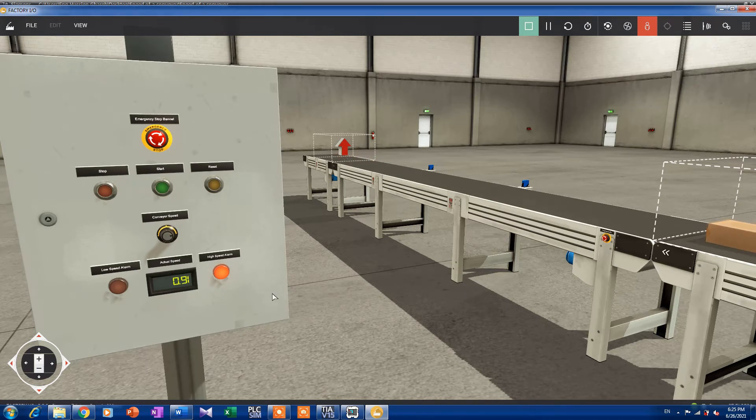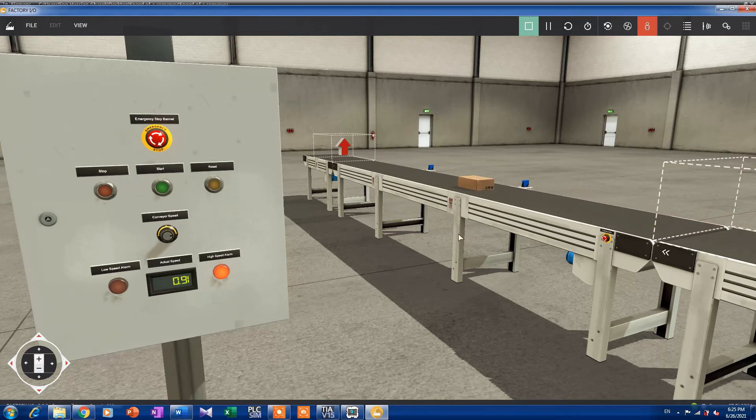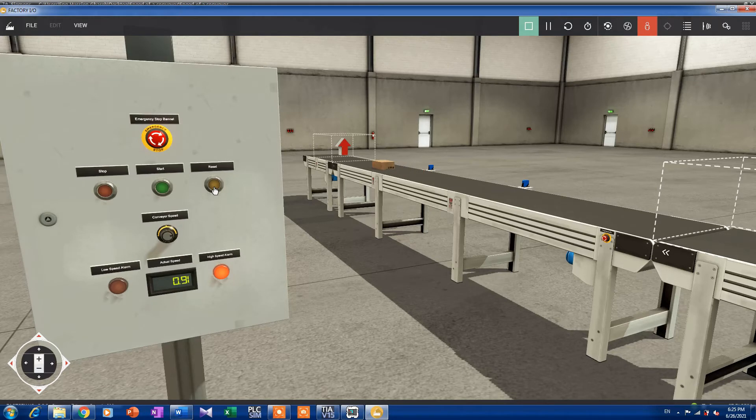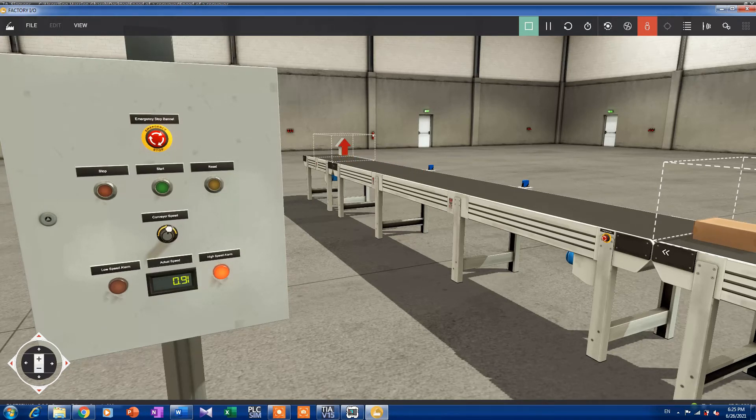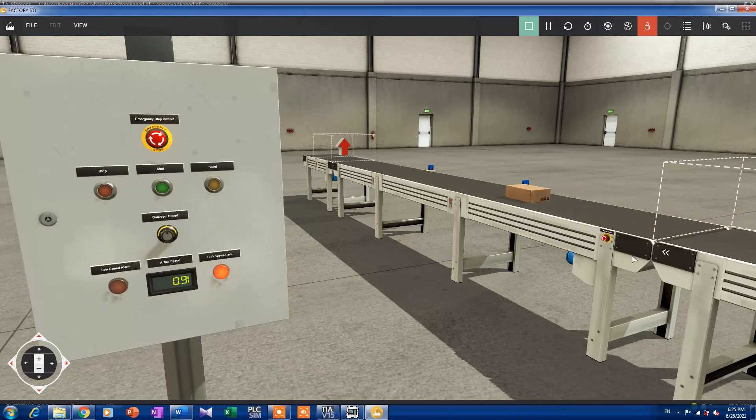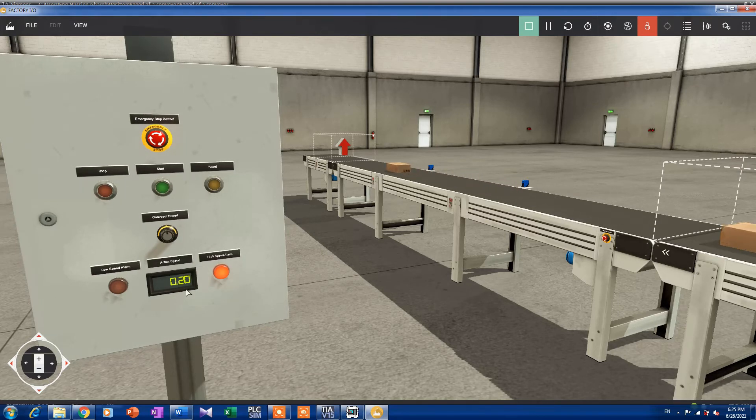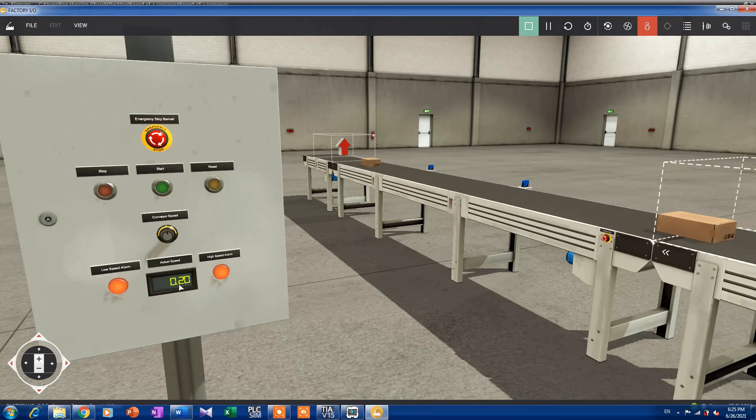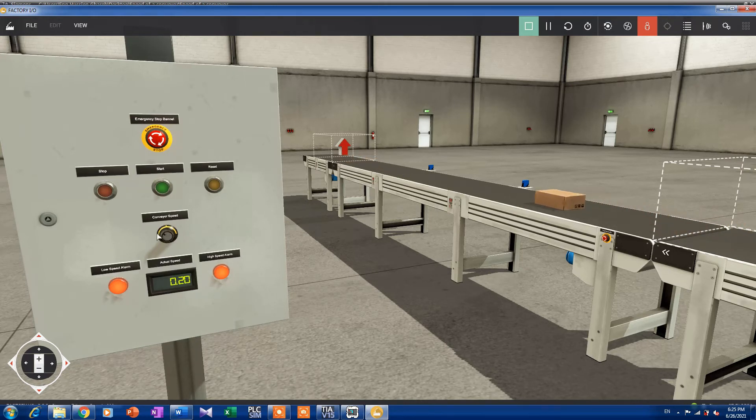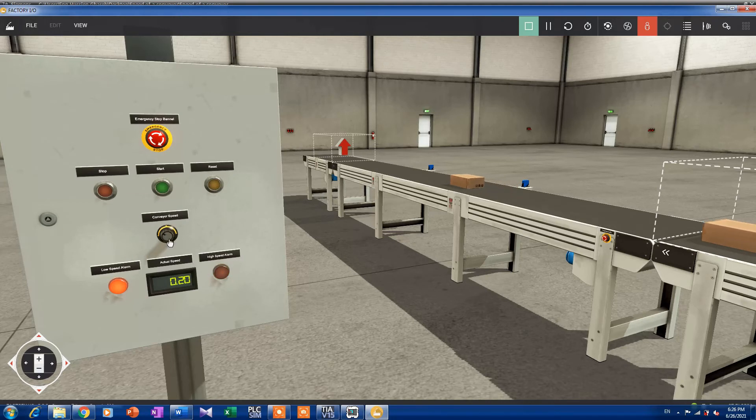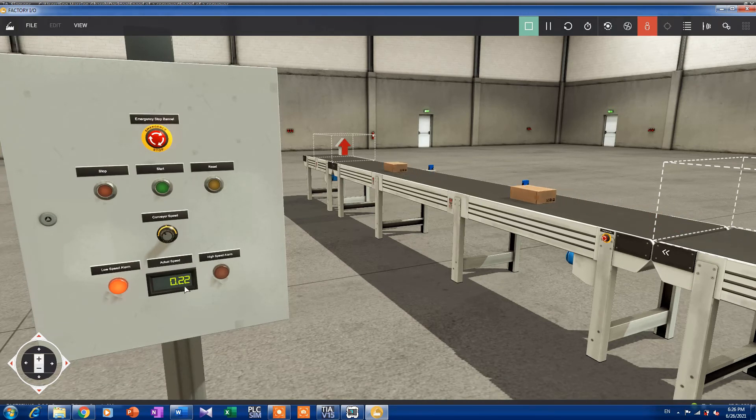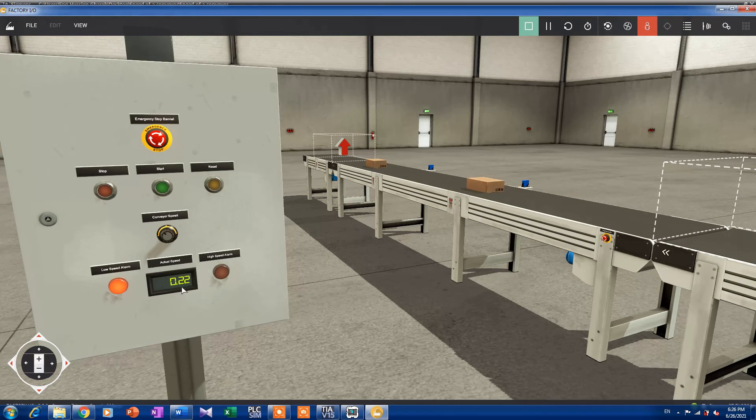Let's go there and see what's going on. We will try to reset but it will not be reset because the alarm is still here. Let's try to decrease the speed a little bit. We can see that the speed now is 0.2 and we have a low speed alarm. We can reset, the high speed alarm is gone, but the low speed alarm is still here. The speed is 0.22.